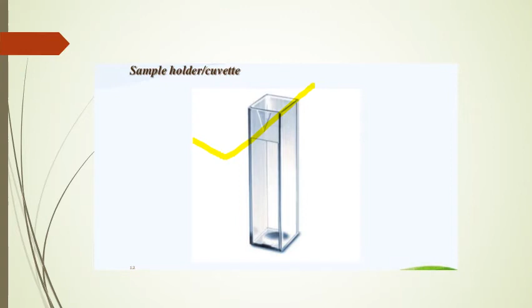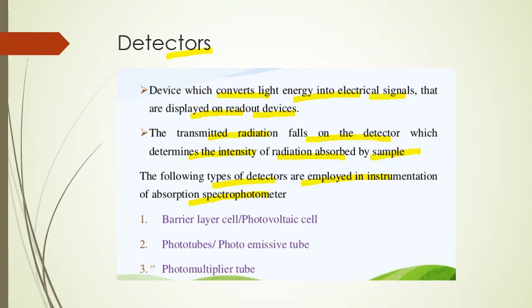Next comes the detector in UV visible spectroscopy, the device which converts the light energy into electrical signals that are displayed on the readout devices. The transmitted radiation falls on the detector, which determines the intensity of the radiation absorbed by the sample. The following types of detectors are used in the UV visible spectrophotometer: the photovoltaic cell, also called the barrier layer cell, the phototube or photoemissive tube, and the photomultiplier tube. So on the basis of the transmitted radiation falling on the detector, it determines the intensity of the radiation absorbed by the sample.